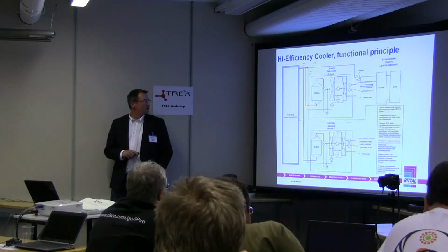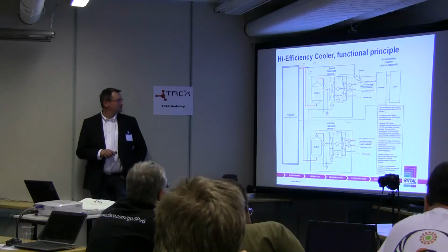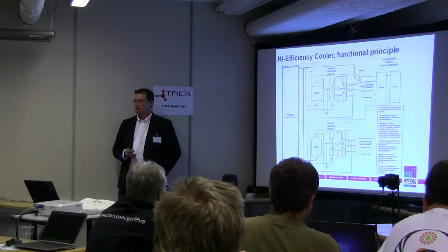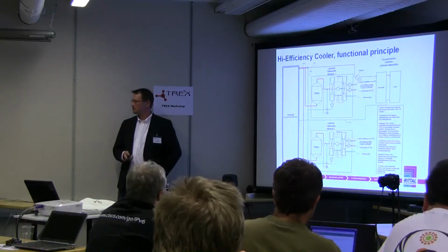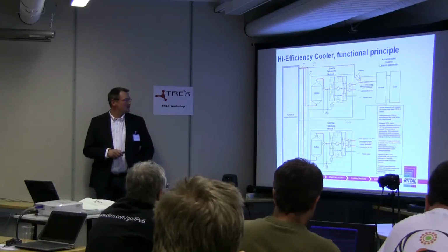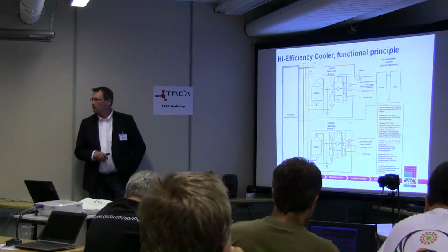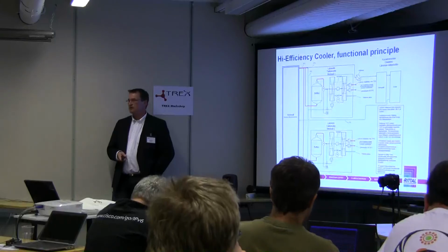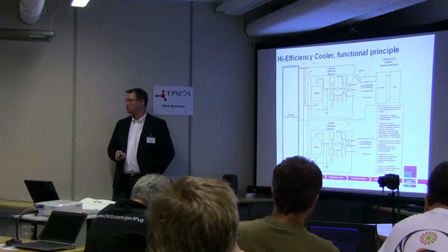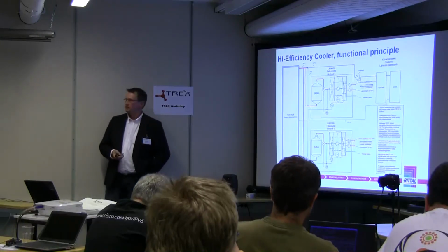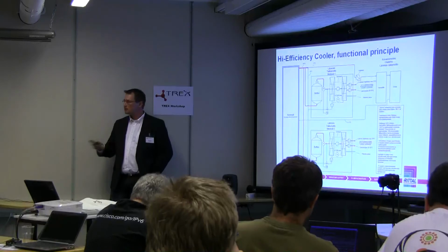And here we have this heat recovery module with buffer tank. This is modified from ground cooling or thermal heating as used in houses. A little bit modified, and the result we get with this solution is, for example, warm house water, maximum temperature 70 degrees, fair enough for a normal house. Or we can use it directly for heating. Basically we are able to get warm water to use in another system for warming up.